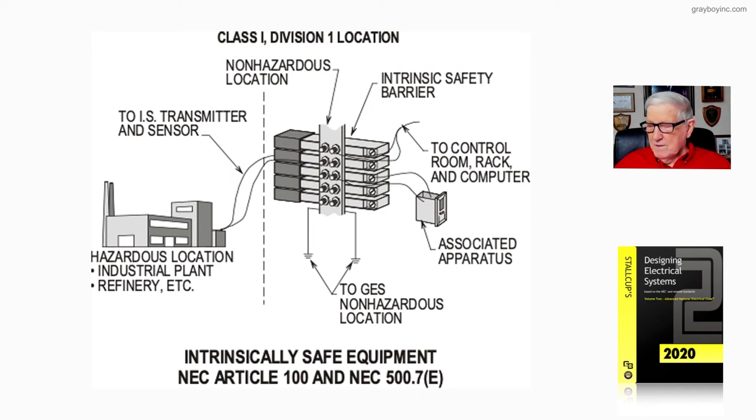You can review Stallcup's Volume 1 on Designing Electrical Systems, starting around page 4-12, beginning with figure 4-20. That series of illustrations shows how intrinsically safe equipment should be installed in accordance with article 504 — which is essentially what figure 501-18 is illustrating to the designer and installer.